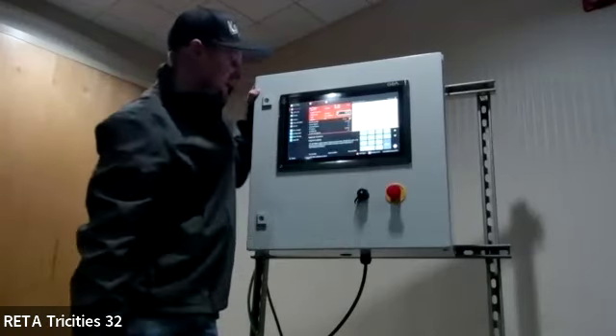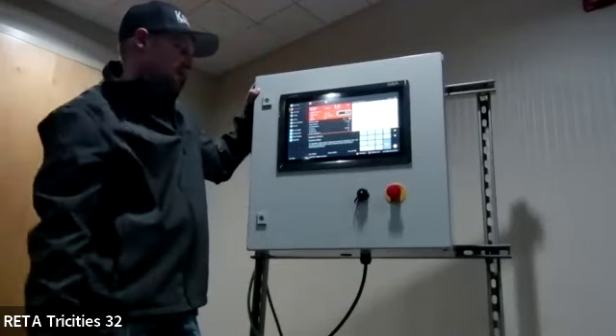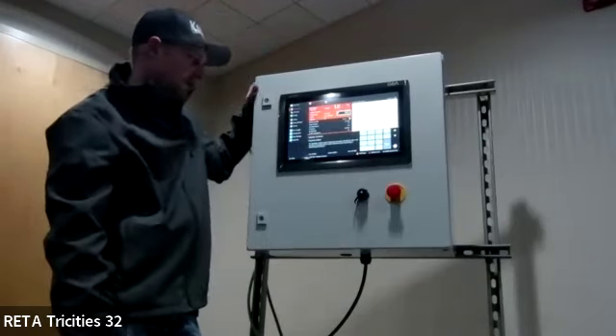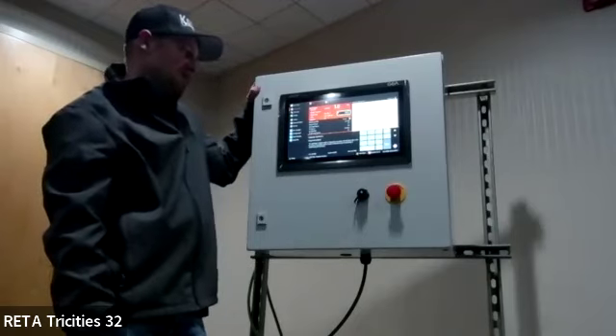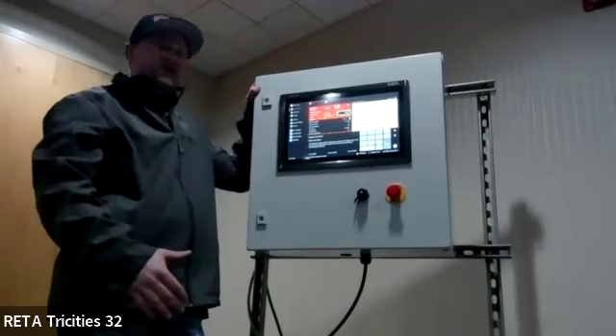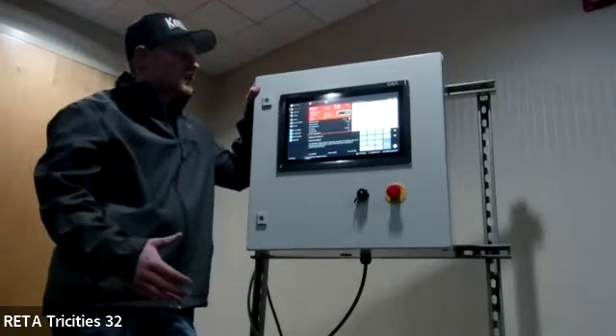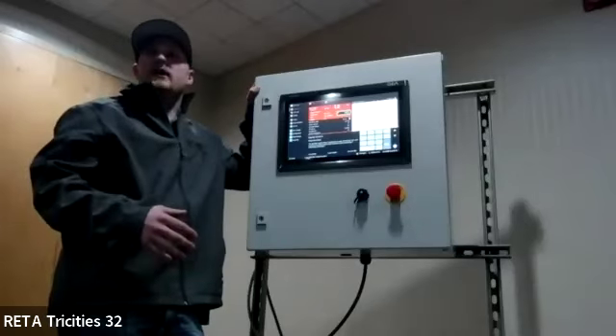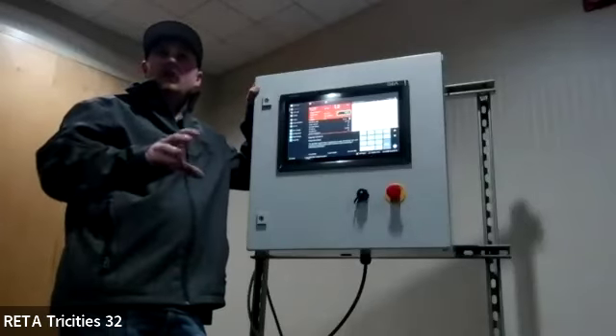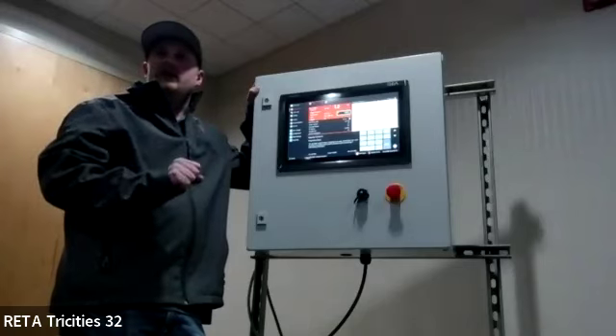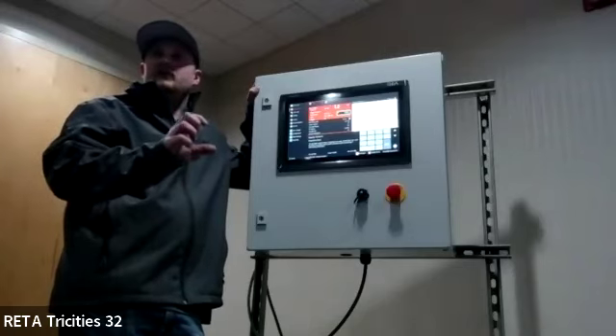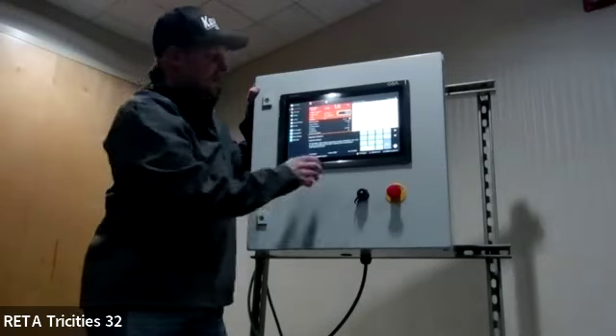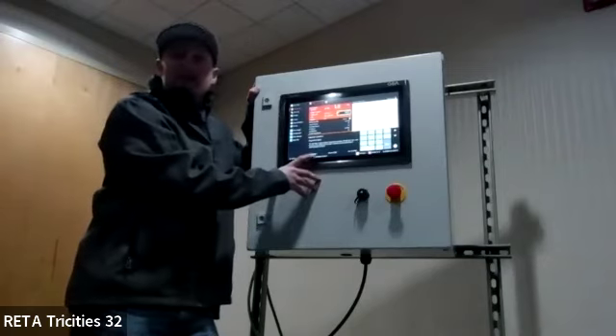The proportional band is the range above and below the set point within which the width of the capacity control pulses is reduced to avoid overshooting or undershooting the set point. So the proportional band is basically the range within which it will pulse the load and unload solenoids to try to maintain that suction pressure as close as it can. And you can also set that to a minimum of 2 PSID.